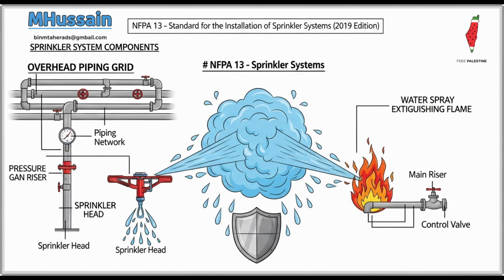And crucially, they added a completely new dedicated chapter focused on alternative approaches for storage. This directly addresses the need for guidance on performance-based design, especially when you're dealing with highly specialized or unique storage arrangements that just don't fit neatly into the standard prescriptive tables. And finally, probably the most interesting update, maybe because it was driven entirely by modern architecture, the rules for cloud ceilings. Yes, the reality of modern design elements hitting the fire code. Cloud ceilings, those decorative non-continuous ceiling panels, they just don't block heat in the same way a continuous ceiling does. So, based on a Fire Protection Research Foundation project, new prescriptive design language was added, allowing sprinklers to actually be omitted above these cloud ceilings.